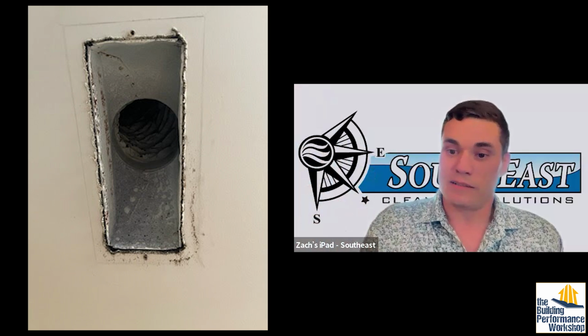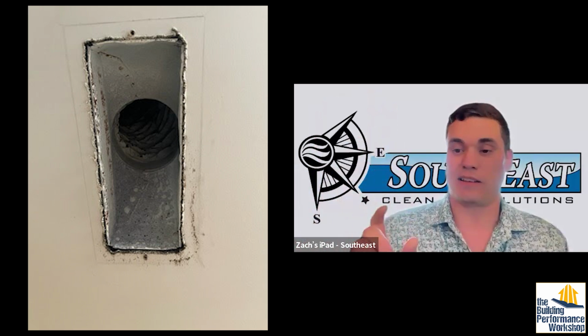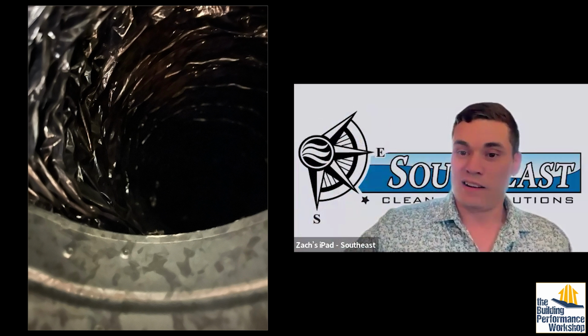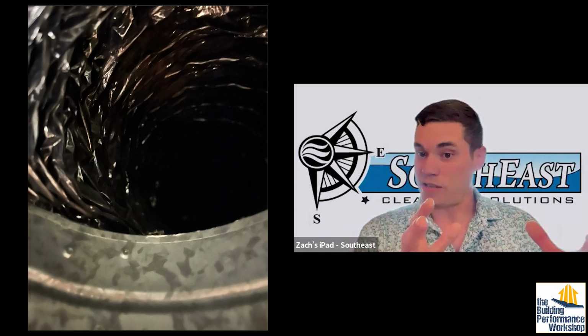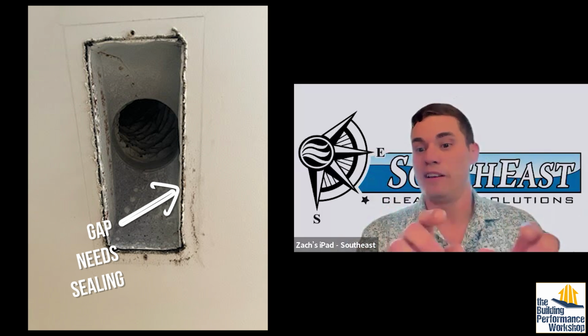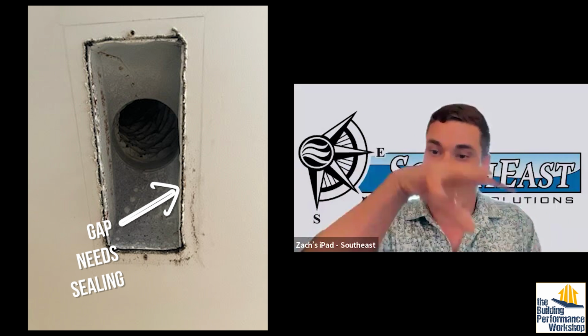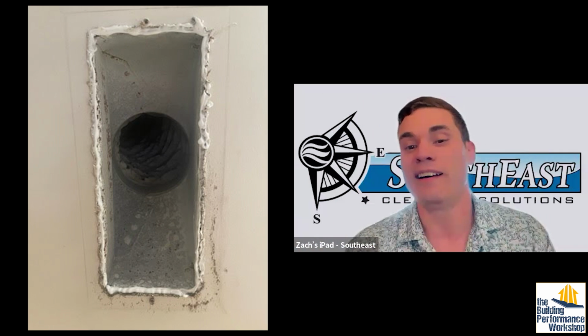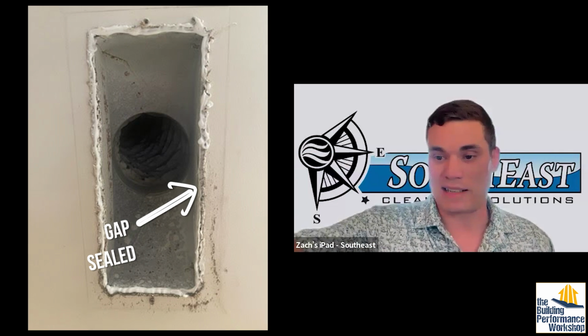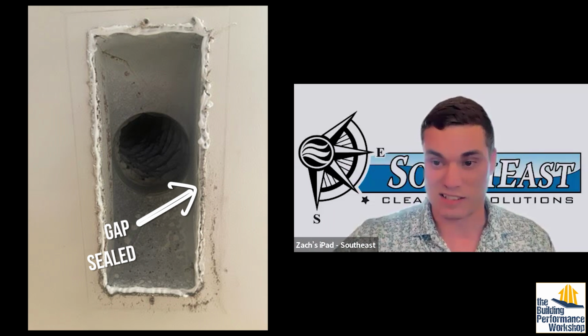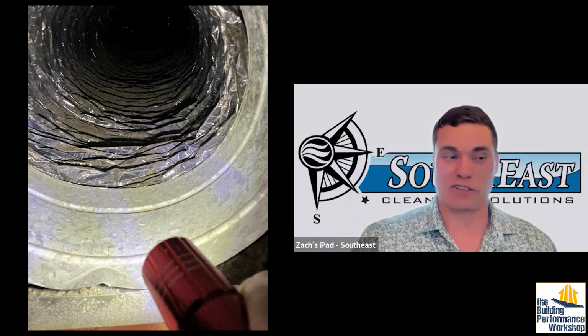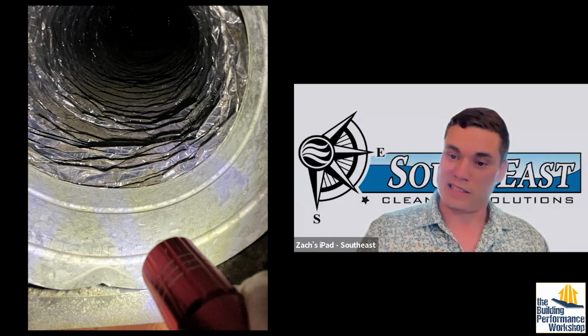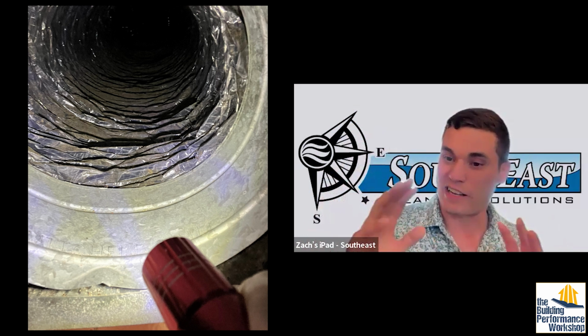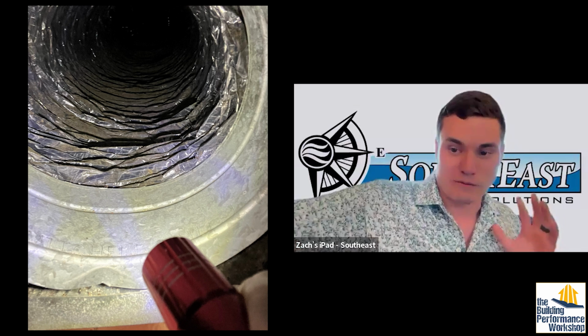If you're handy and you can actually pull one of those vents down, stick your phone up and take a picture inside of the duct where it goes back, because most of the time it's going to be that vent boot gap, isolated there at the friction point right at the end of the run. But sometimes it's all the way back to the air handler and it's actually throughout the system. That's why you take the picture down the line, to see: is this a 2 foot issue that I can reach, or is this a 10-foot issue that is beyond my capabilities as a homeowner?